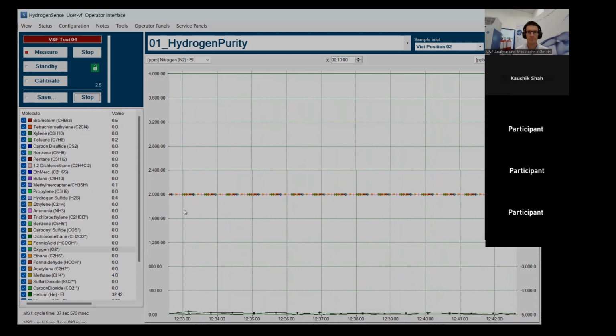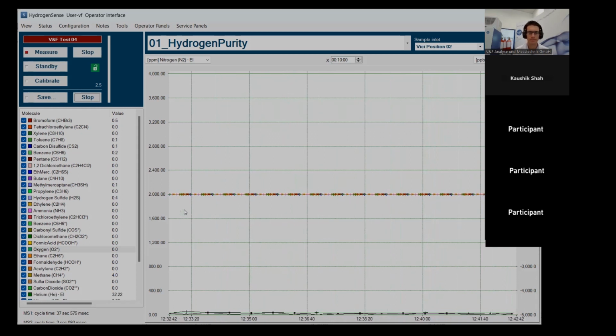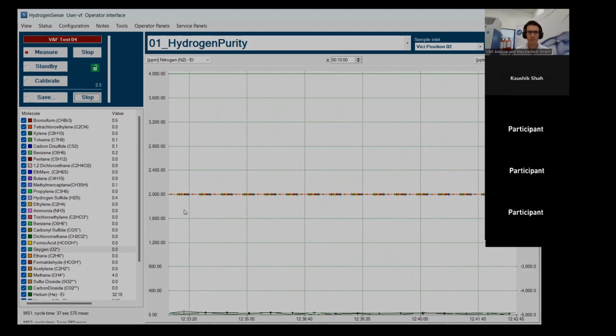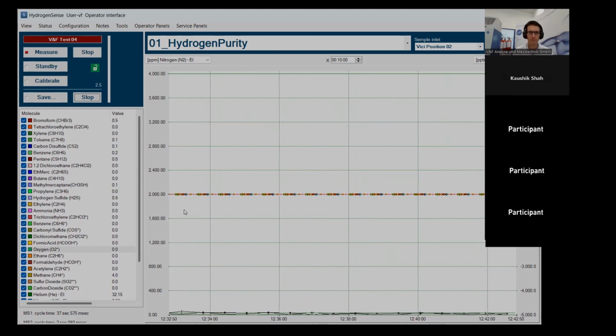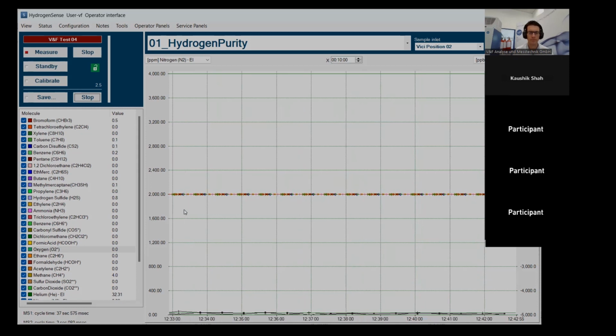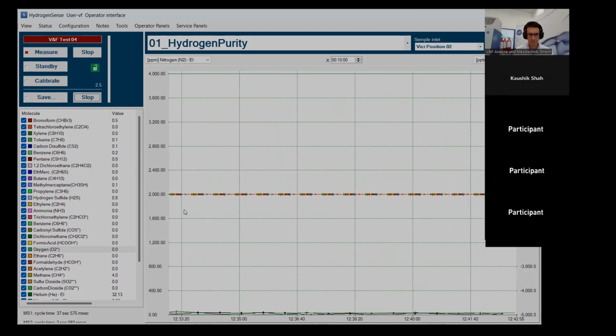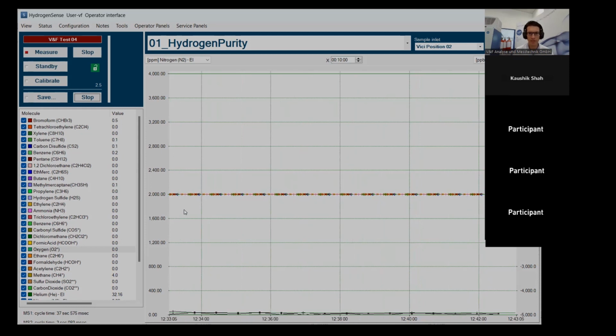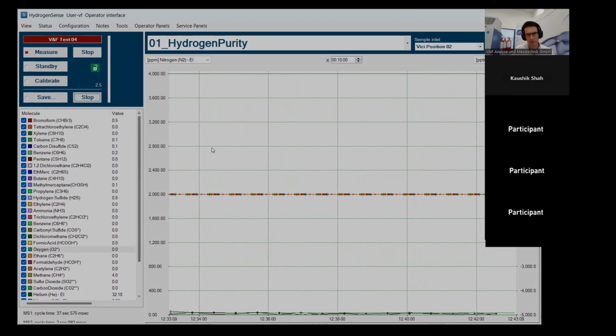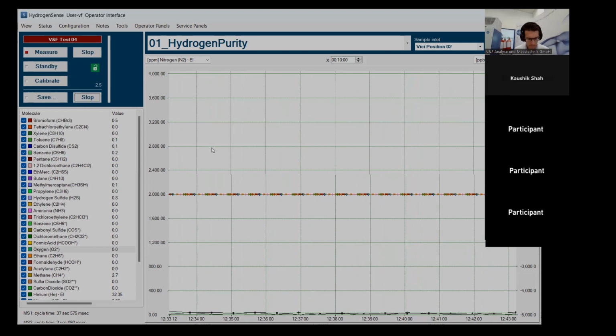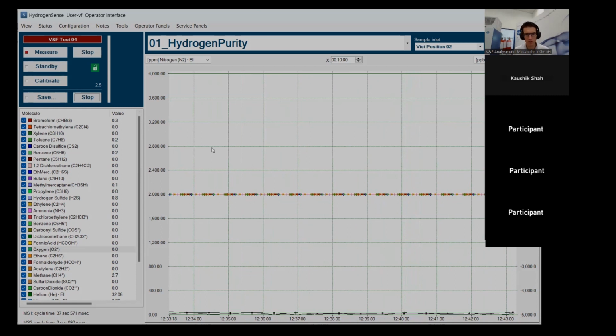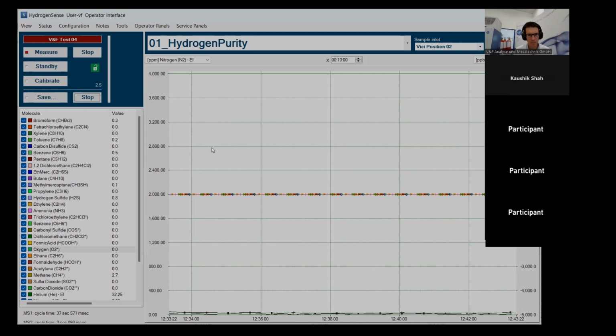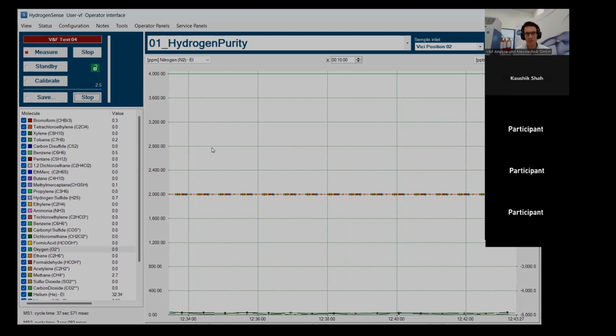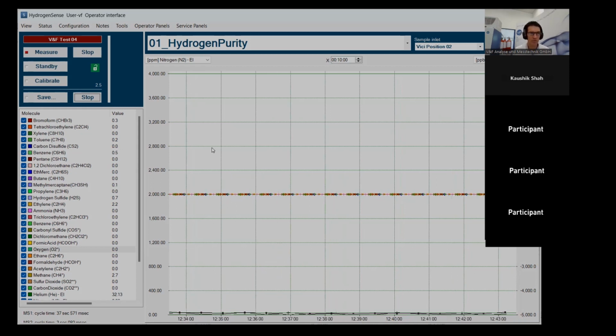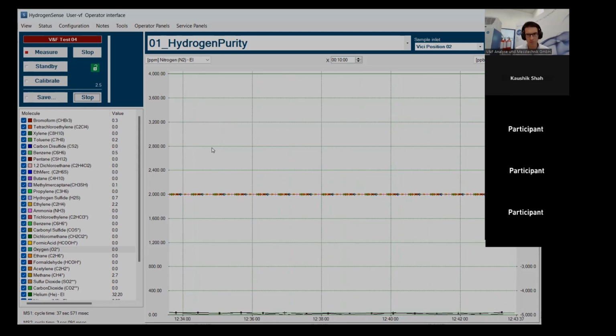My one question related to the previous questions. In case you are using it offline, keeping your instrument in the laboratory area, typically if I am collecting a sample in a 500 ml sample cylinder at about 5 kg pressure, will it be able to give the right, precise and trusted result? That's something that needs to be calculated. Right now I'm running 500 milliliters per minute. Let's say I need 15 minutes of analysis time, including flushing and then doing the measurement analysis. That would mean I need at least 7.5 liters of gas. At a 500 ml container, that should be roughly 15 bars of pressure. So I would rather go to 20 bars of pressure in order to have enough gas to do the analysis.